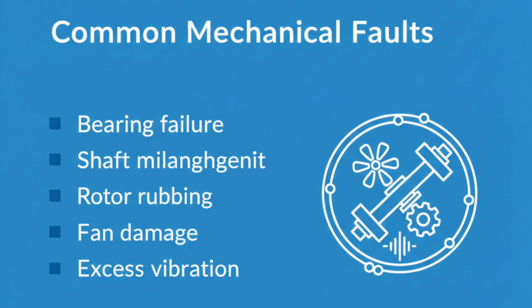Mechanical faults are just as serious. Bearing failure is one of the most common causes of motor shutdown and usually produces grinding noise and temperature rise. Shaft misalignment between motor and driven equipment causes vibration and bearing damage. Rotor rubbing against the stator, cooling fan damage, loose foundation bolts, and bent shafts all contribute to mechanical instability and efficiency reduction.